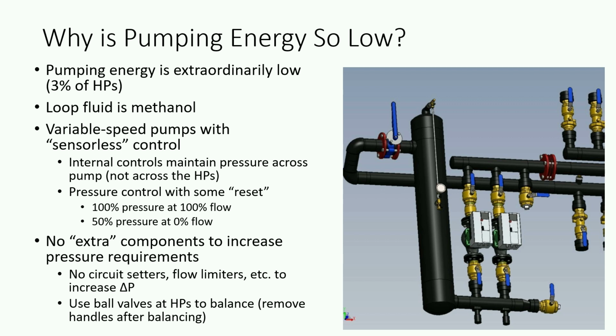I did a lot of geothermal variable speed pumping papers about 20 years ago. Back then, engineers loved to put valves in things like circuit setters and balancing valves, and all that adds pressure drop. It means your delta P across the heat pumps has to be bigger to overcome all that, and it kind of hurts performance. So this system did not have any of these extra components.